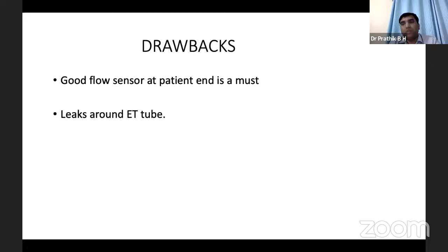And if there is a large leak around the endotracheal tube, then you have to replace the endotracheal tube, especially if the leak is more than 30%. This again is compensated with the newer ventilators like VN500, which has a leak compensation mechanism of up to 70 to 80%. In conclusion, it is volume trauma which is the critical determinant of ventilator-induced lung injury.